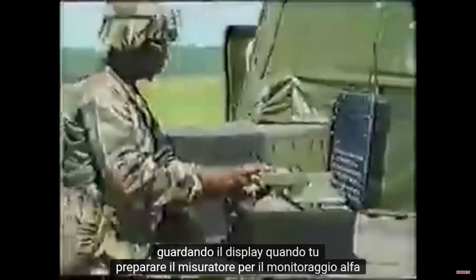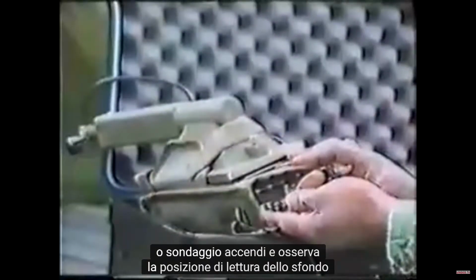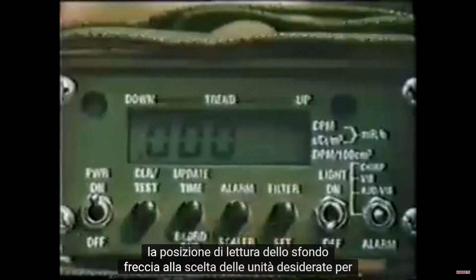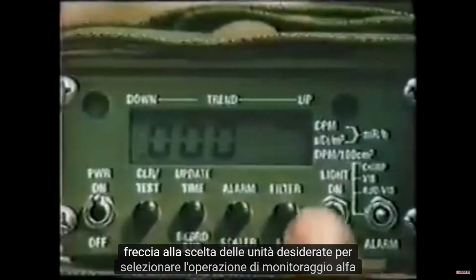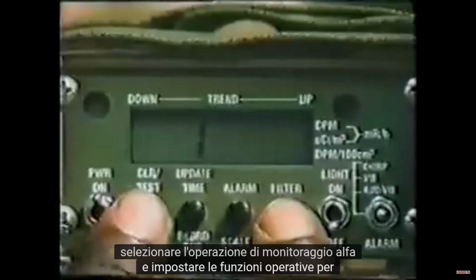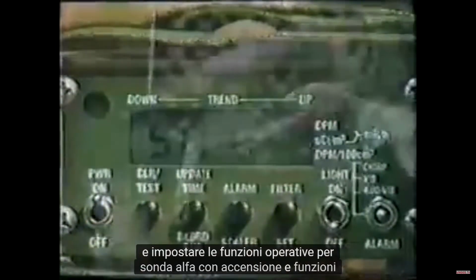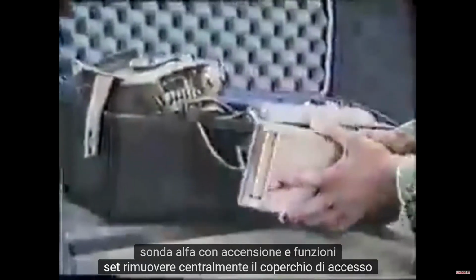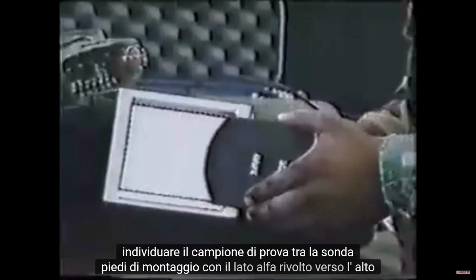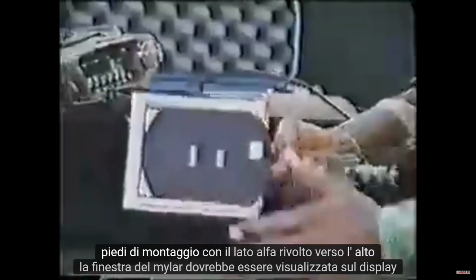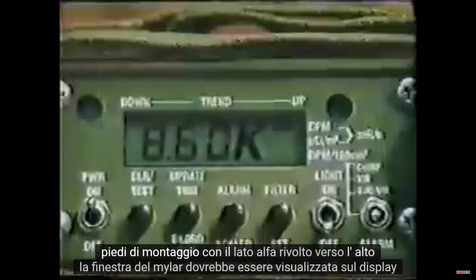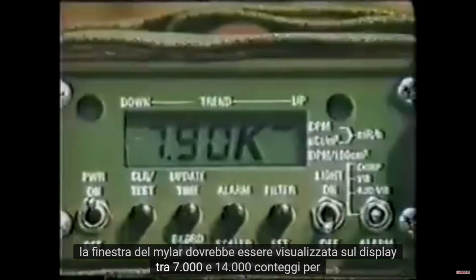When you prepare the meter for alpha monitoring or survey, turn the power on and observe the background reading. Position the arrow to the choice of units desired for the alpha monitoring operation. Select and set the operating features for the alpha probe. With power on and features set, remove the access cover. Centrally locate the test sample between the probe mounting feet with the alpha side facing the Mylar window. The display should read between 7,000 and 14,000 counts per minute. Remove and replace the test sample in the case.